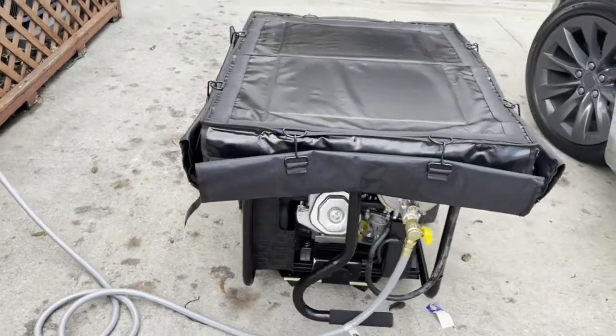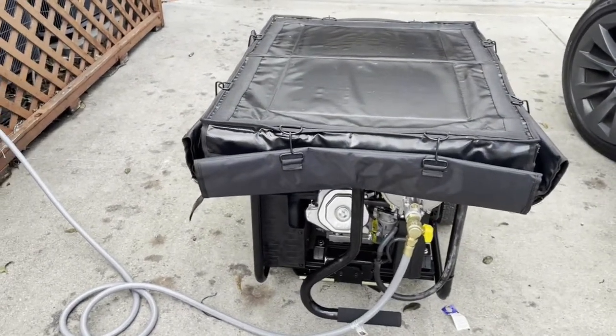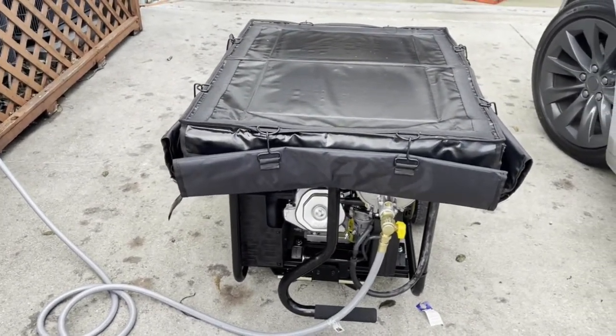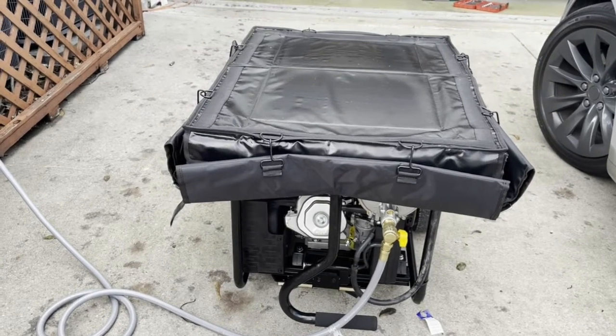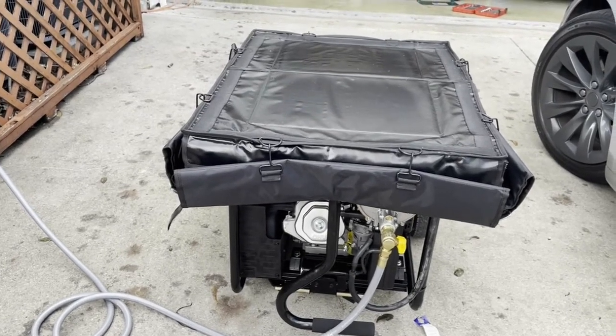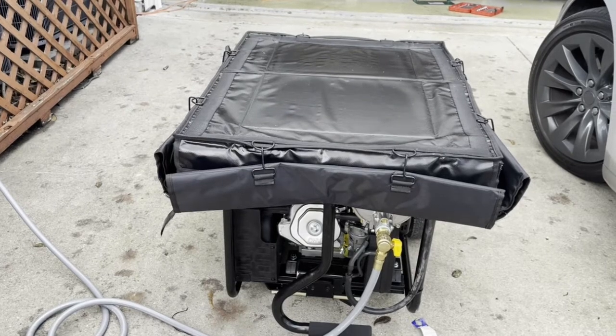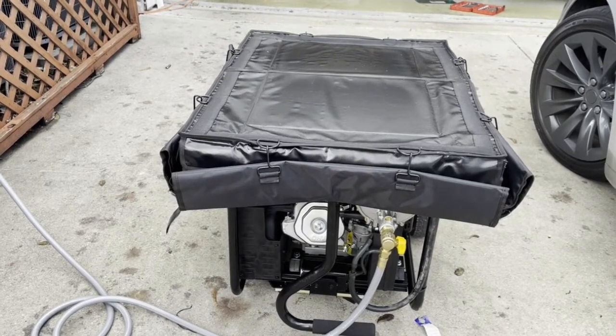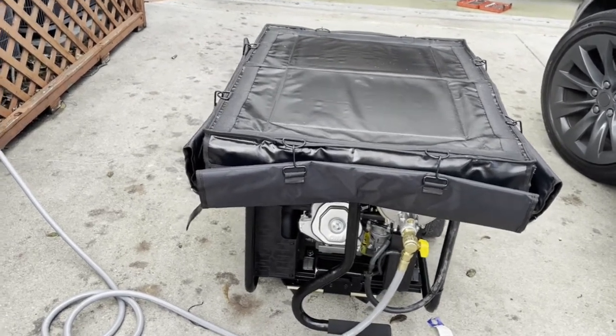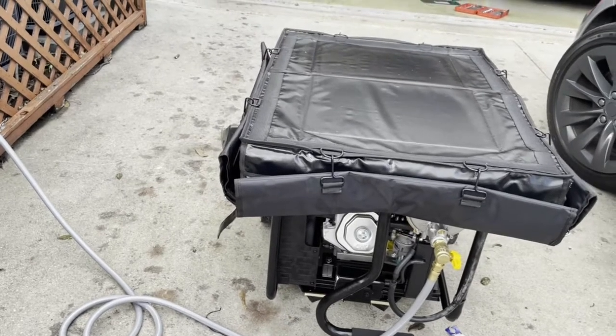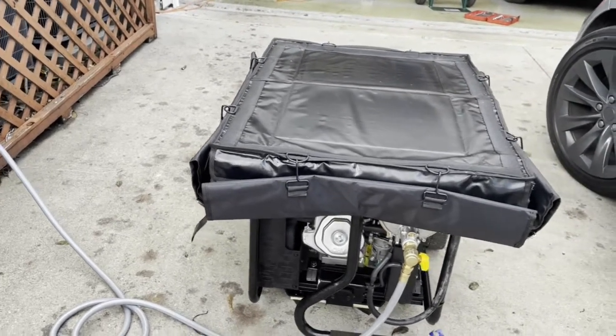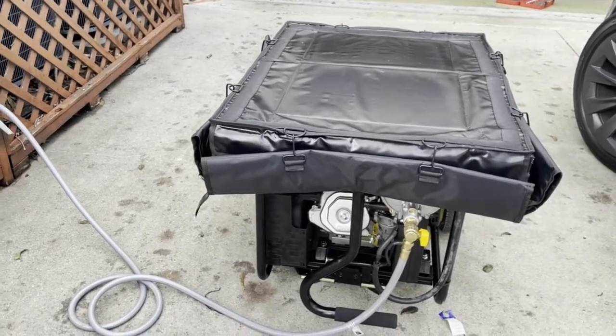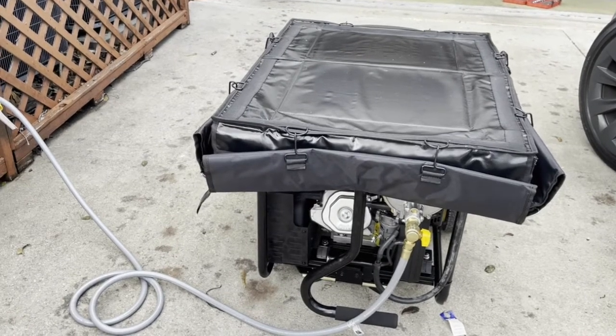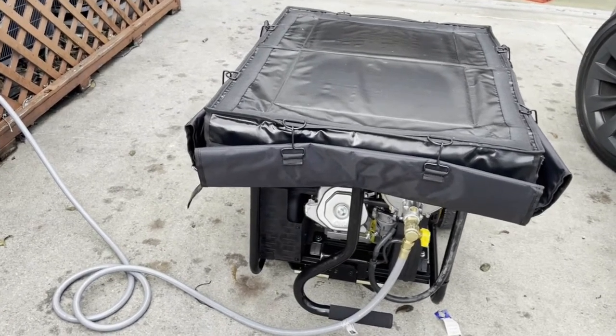I have a 1/2-inch hose, 10 feet long. The suggested maximum distance if using 1/2-inch hose is 10 feet for this engine, which is 13 horsepower. If you have a bigger generator, more than 7,000 watts, and need a longer distance, you will need to upgrade to 3/4-inch hose.